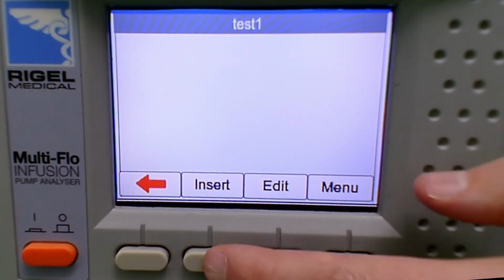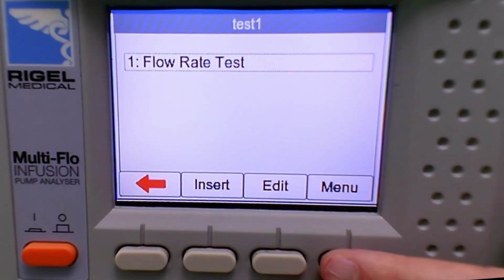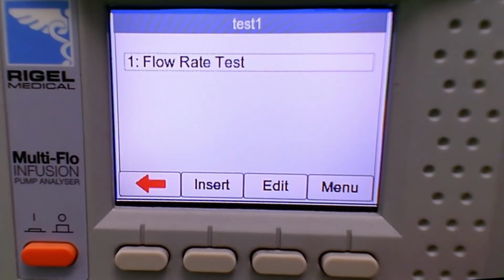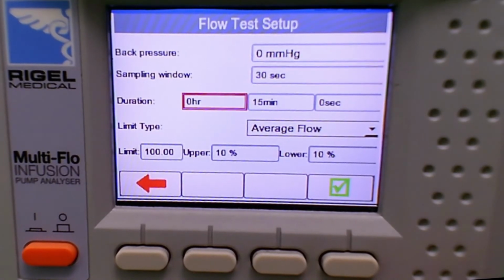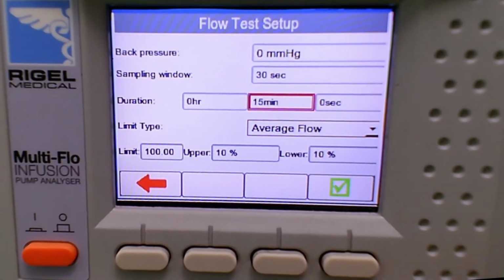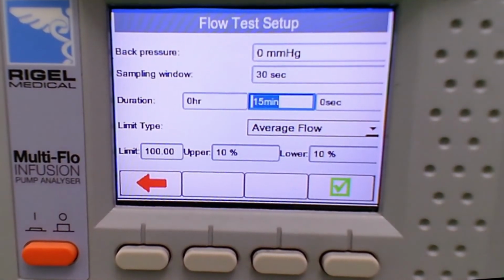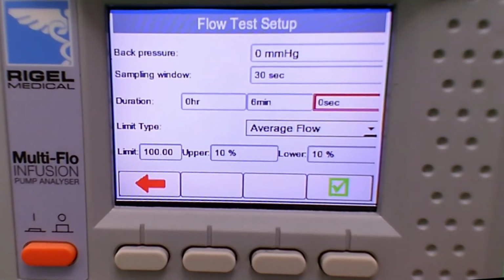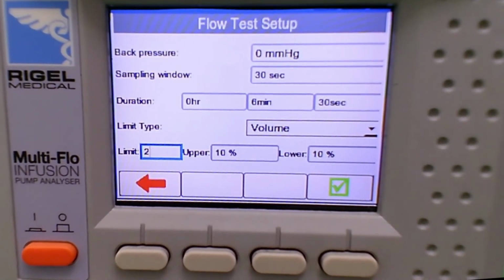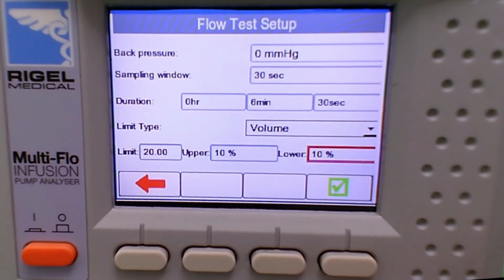F3 is to edit, function key F3, and we can insert new tests. So we'll insert a flow rate test. Again, we'll use similar parameters, but we'll set the duration to a little bit less, so we'll set this to 6 minutes, 30 seconds for demonstration purposes. We're measuring volume, see a limit type. So the first test, say if we wanted to do 2 volume tests, we're going to set 20 first, and the Alaris SE has a 3% error for the PM.